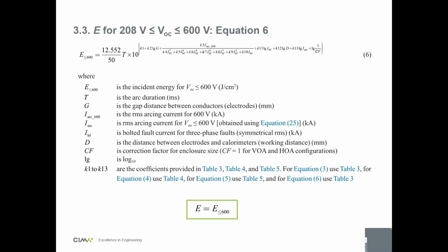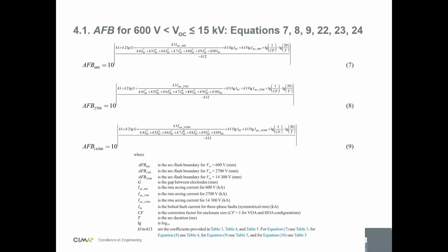But now if you're below 600 volt, the equation is simpler. You don't have to calculate 3. You only have to calculate 1. So for energy, you need to put your fault current, your arc time, your distance between phases, your working distance, correction factor, K factors, so the same parameters, and then your final energy is just that value. So this is the biggest equation of them all.